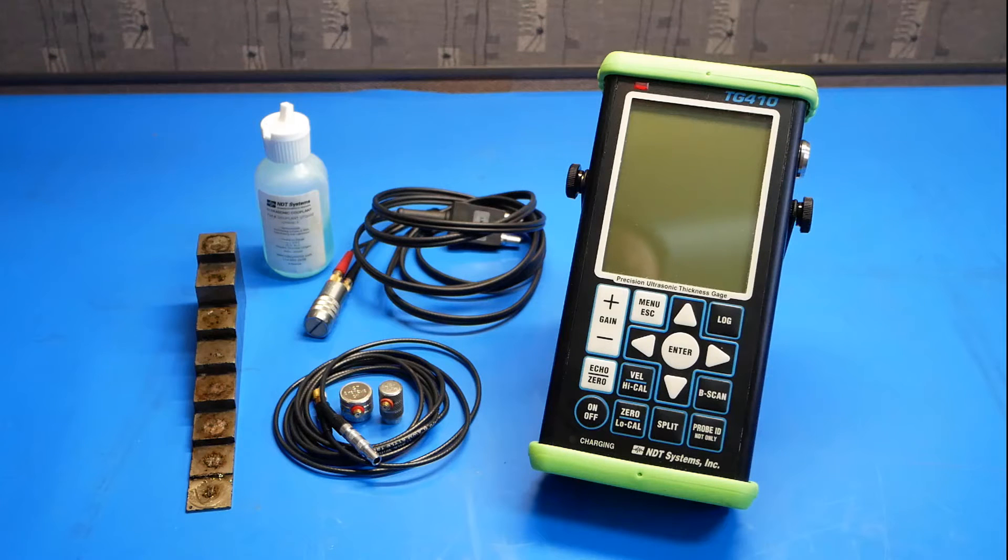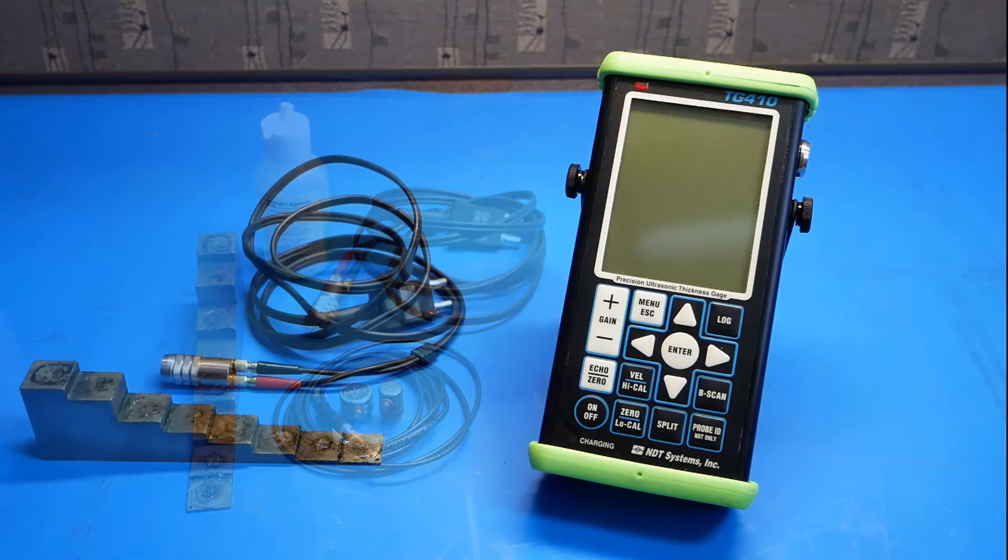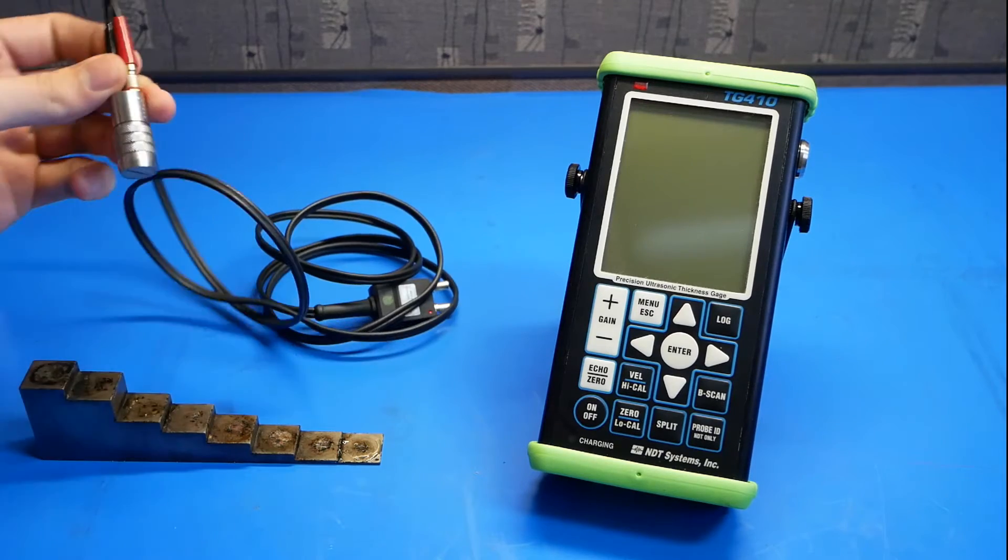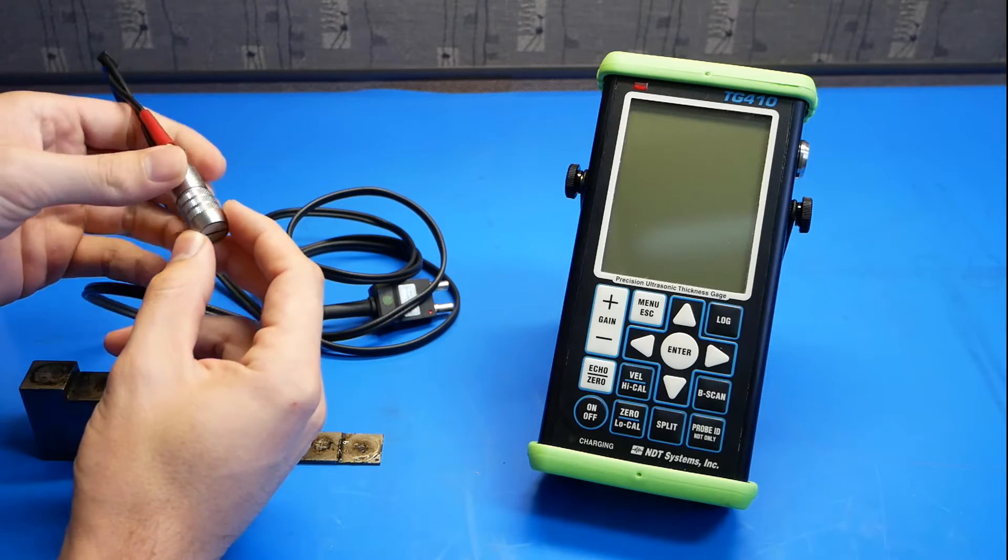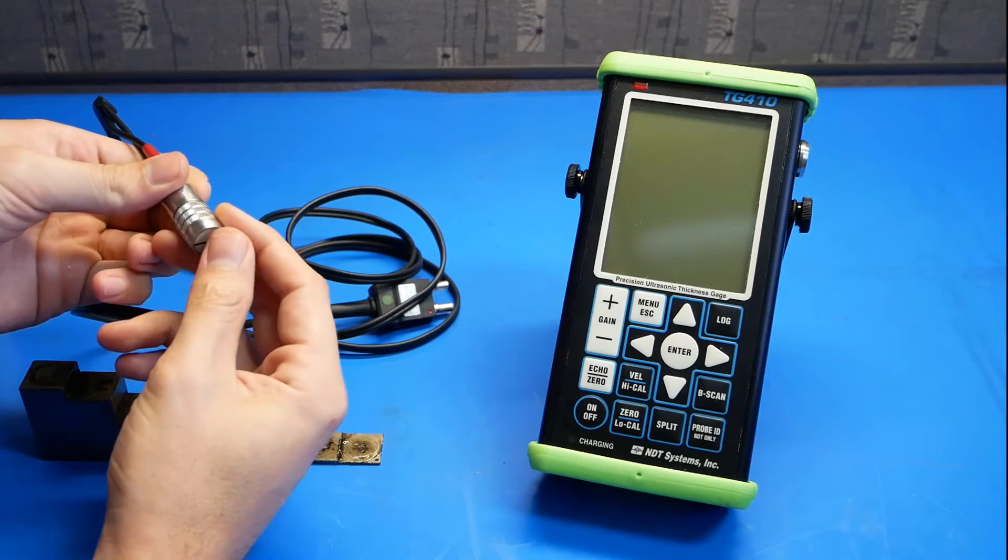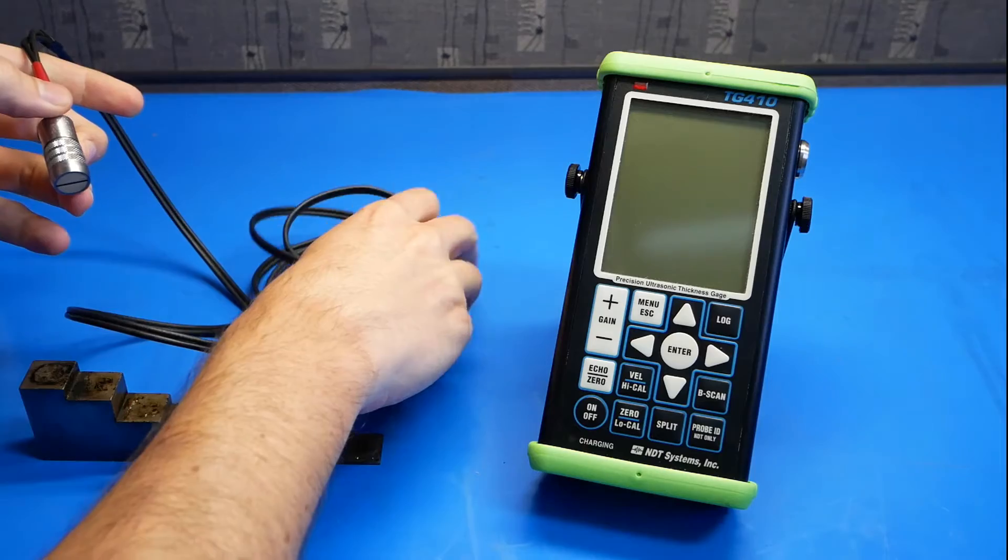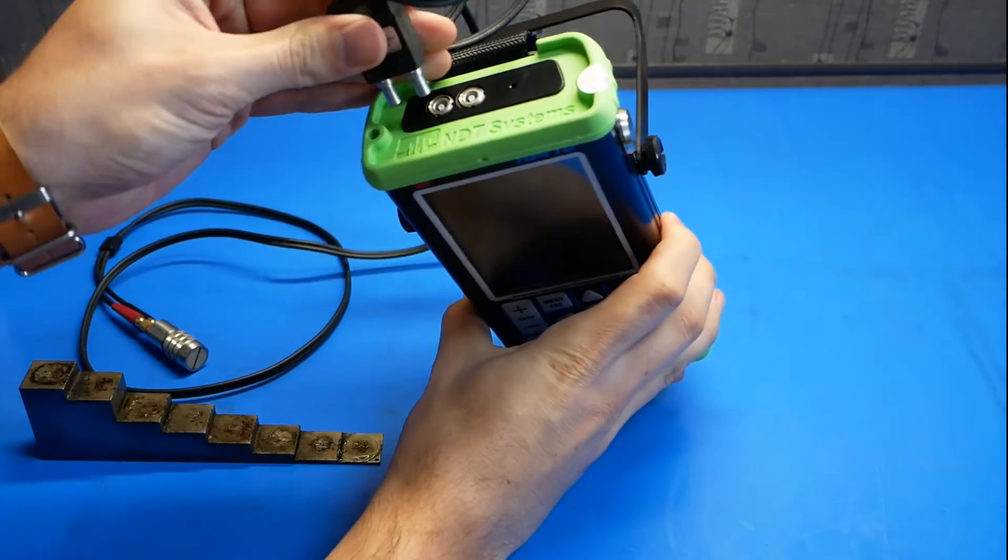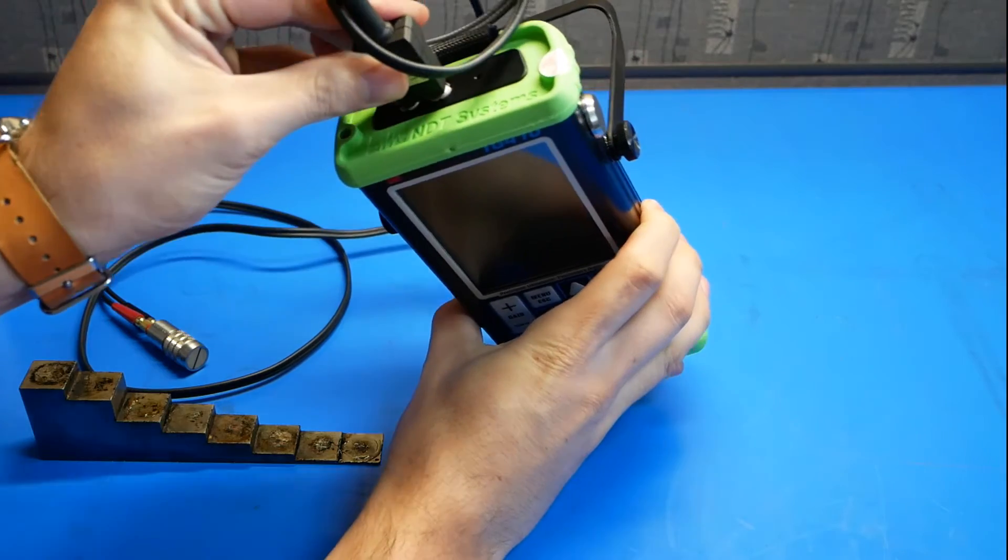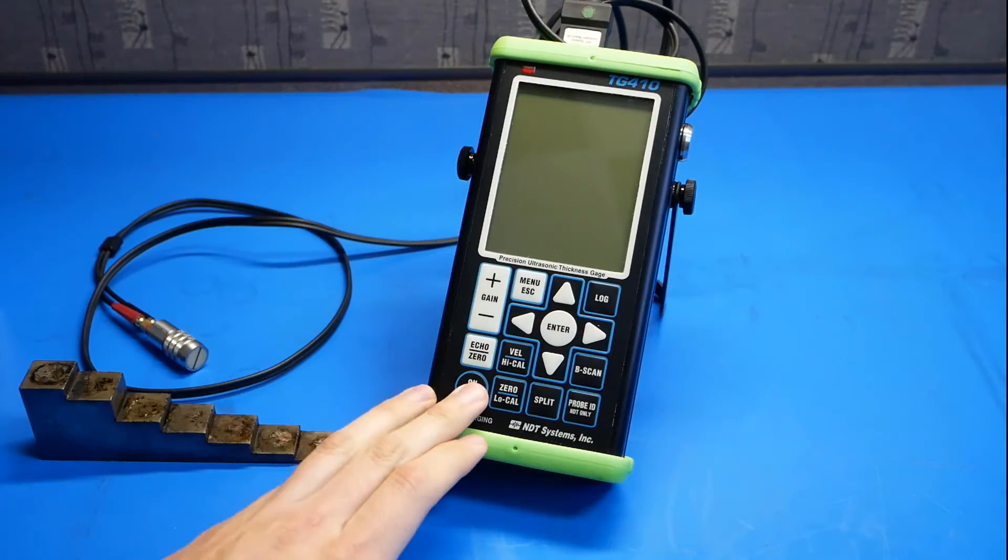Let's get started with the dual element probe. This dual element probe is a TG506. It's 5 megahertz and has a 0.375 element diameter. To get started, we'll go ahead and plug it into the gauge. We'll turn the gauge on.